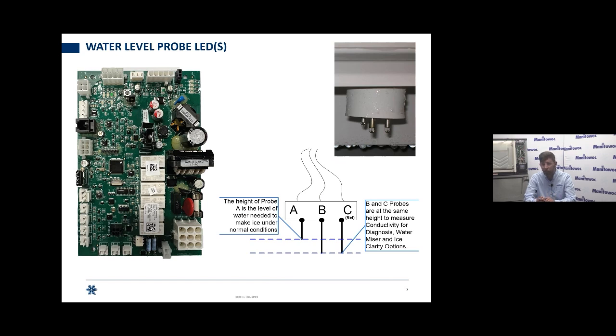Water miser on the old Indigo, or the use less water with reverse osmosis, as you'll see on the Indigo NXT. It's the same on Indigo as it is on Indigo NXT, or the ice clarity feature. So as we fill up with water and we touch those 2 longer sticks, that LED will light up. If you were looking at your user interface display, it shows service, data, real-time data, and inputs, because again, this is an input device. You'd see that water level low went from not sensing to sensing.